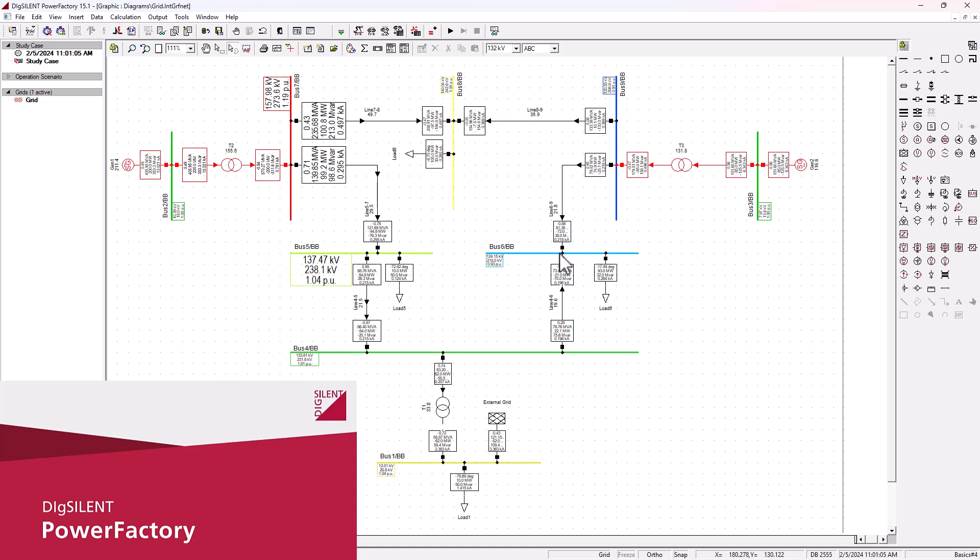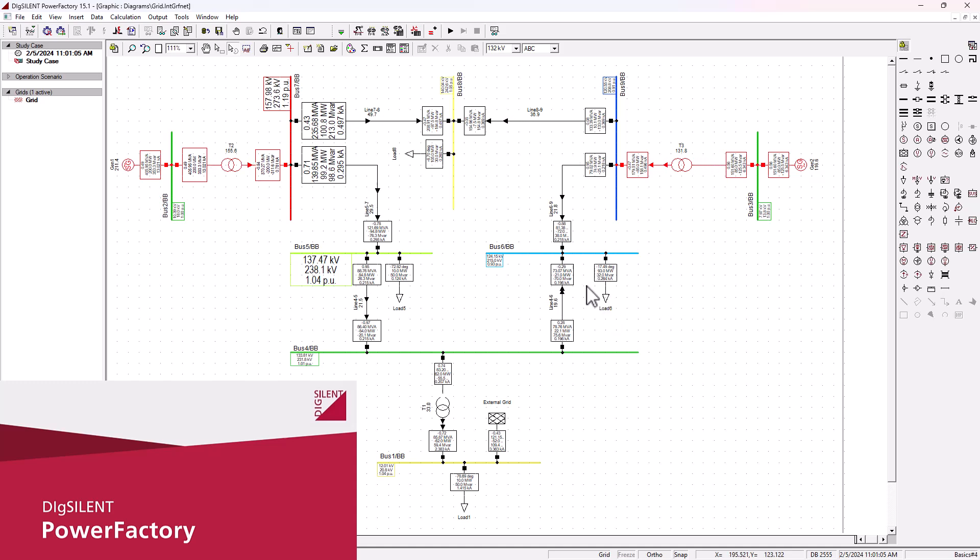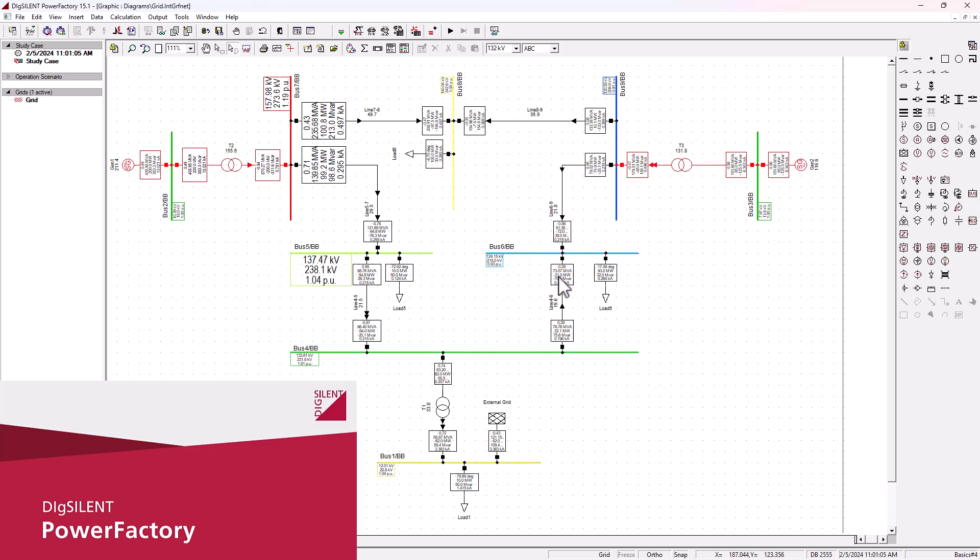As you can see, this busbar 6 supplies this load 6 here, which is a 93 megawatt load. So we've got about 93 megawatts of power that need to flow to load 6. Where is it coming from? We can see there is 21 megawatts coming from line 4 to 6, and on this line here we got about 72 megawatts. Combined, that's giving the 93 megawatts going to load 6.